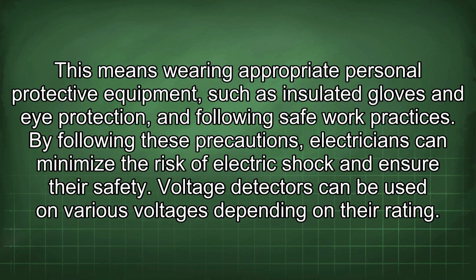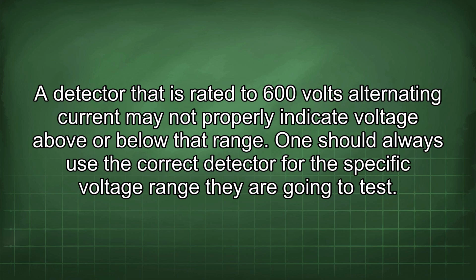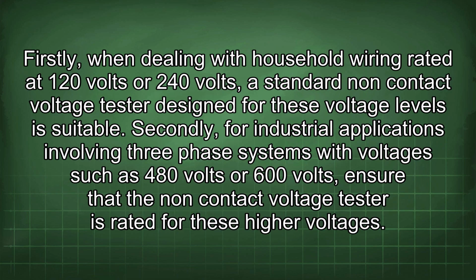Voltage detectors can be used on various voltages depending on their rating. A detector that is rated to 600 volts alternating current may not properly indicate voltage above or below that range. One should always use the correct detector for the specific voltage range they are going to test. Firstly, when dealing with household wiring rated at 120 volts or 240 volts, a standard non-contact voltage tester designed for these voltage levels is suitable. Secondly, for industrial applications involving three-phase systems with voltages such as 480 volts or 600 volts, ensure that the non-contact voltage tester is rated for these higher voltages.